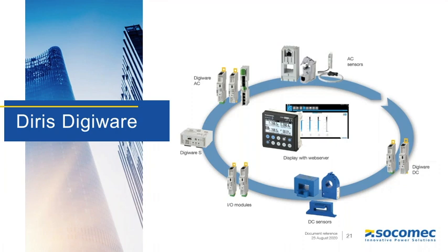At Socomec, we specialize in power monitoring products. On this slide, you can see our Diris DigiWare product line, which allows for smart plug-and-play between modules and current sensors. The modules connect via RJ45 cables, and the current sensors connect via RJ12 cables. We offer the most compact multi-circuit solution on the market, whether for a new installation or a retrofit, inside a panel or outside it in a box. The product is available for AC applications as well as DC applications.